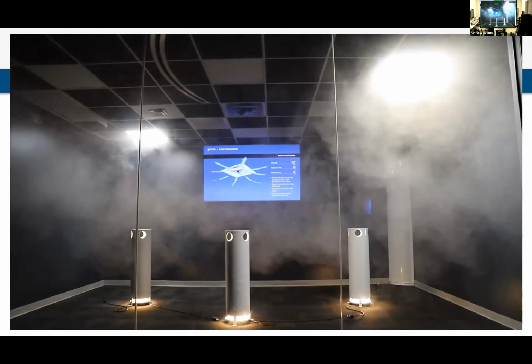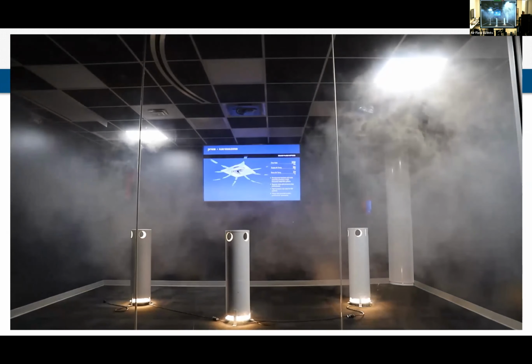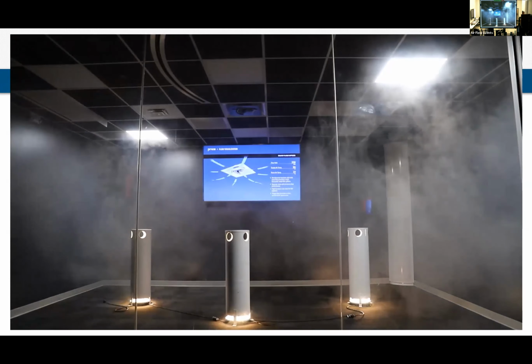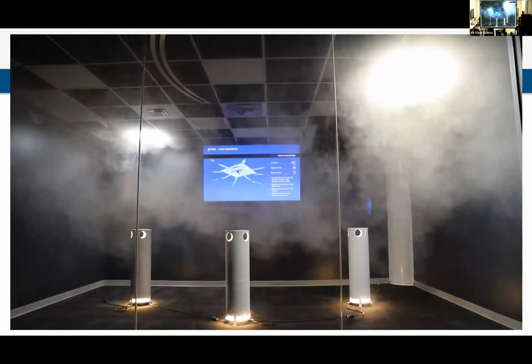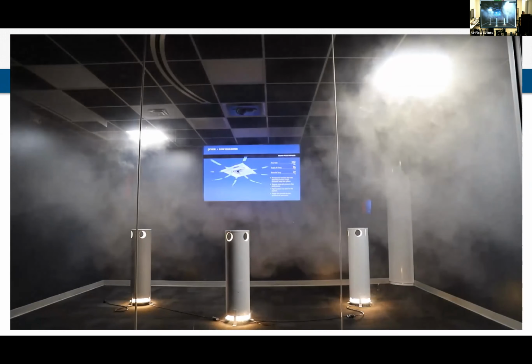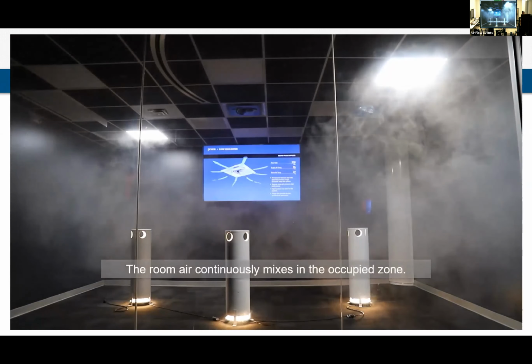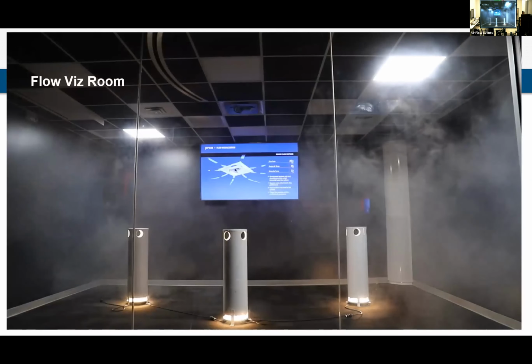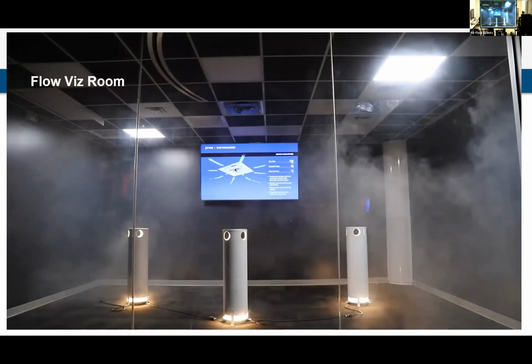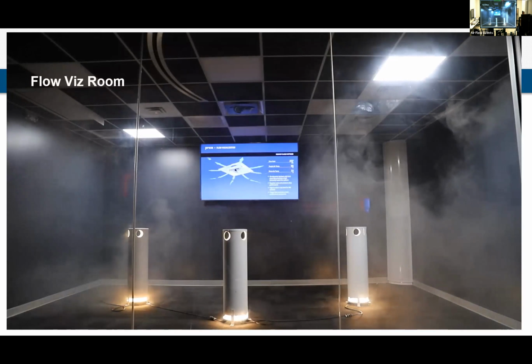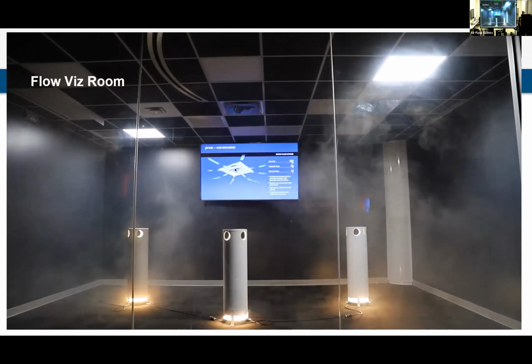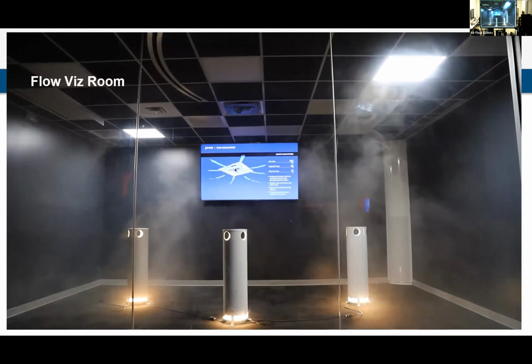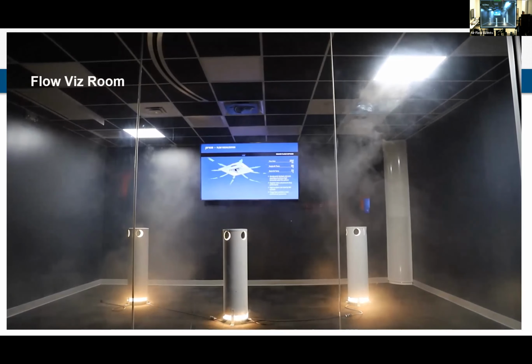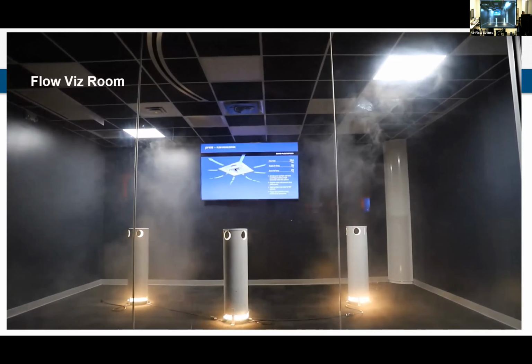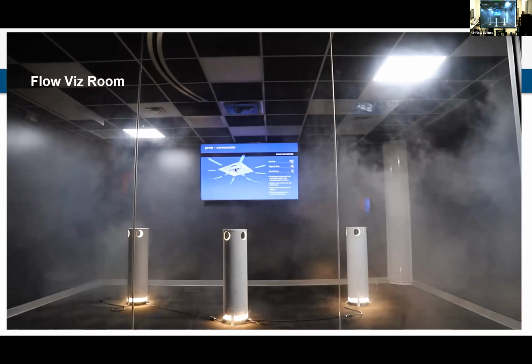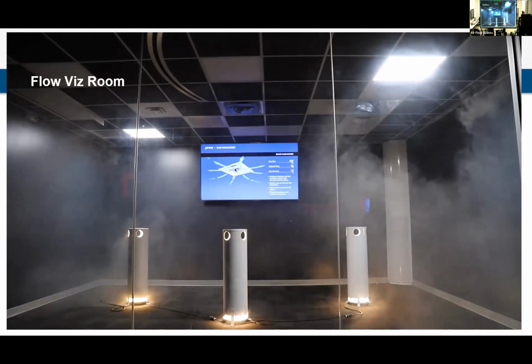You will see some of this smoke now is moving pretty slow, and you might start seeing that circular pattern. So the air is going to start rising back up to the ceiling as it warms up, and we will start to see a mixing in the occupied zone. Here you can really see that well. All of the smoke is slowly kind of moving throughout the space. There are returns in the corners of this room, so you should see the air kind of start to make its way towards the returns in the ceiling. This is what a mixed system looks like.